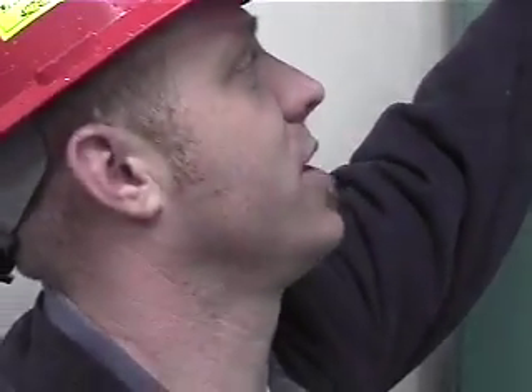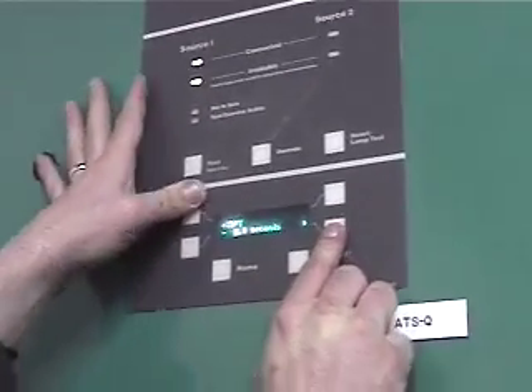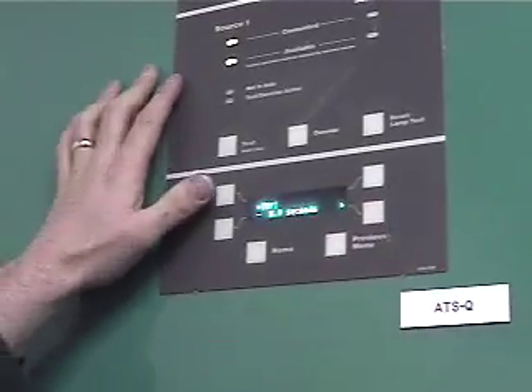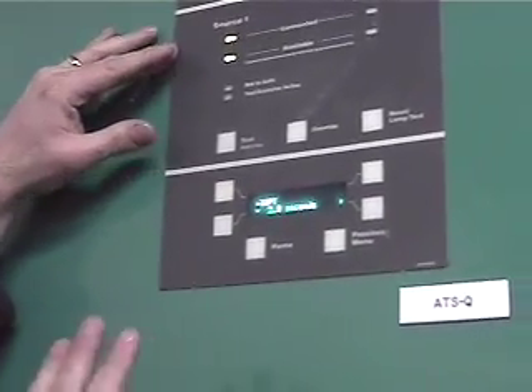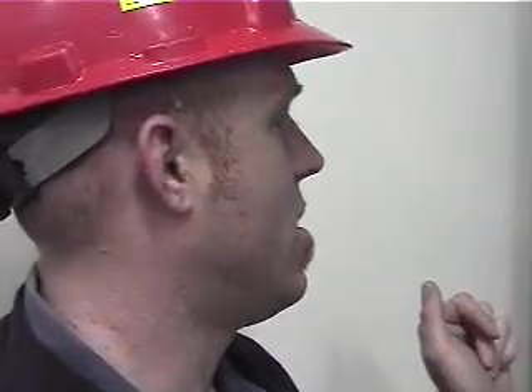There's one other stop we're going to make on the way. This is set up for 0. I'm going to change that. I'm going to give that 2 seconds. This is the time delay program transition, or a neutral time delay. If we transfer inertia loads or inductive loads too fast, we can cause a breaker to trip. So what we do is we let the transfer stop in neutral. It'll sit there for a couple of seconds, then it'll bring our loads back on.